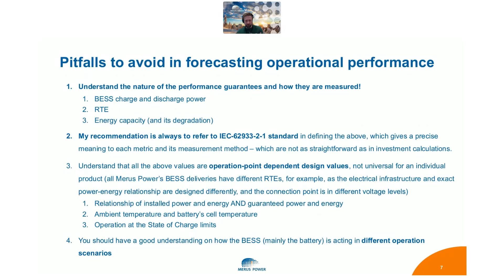So my advice would be to get an understanding of how these values are defined by standard, what the measurement methods imply, and how these change in different operation conditions. And here I want to do an example regarding round-trip efficiency, so you understand how much philosophy is actually crunched into one number. Round-trip efficiency is typically used in investment calculation as the metric of the energy losses of the energy storage, and therefore the lost money based on the energy price on the market. Kind of obvious and important to include it in the investment calculation.